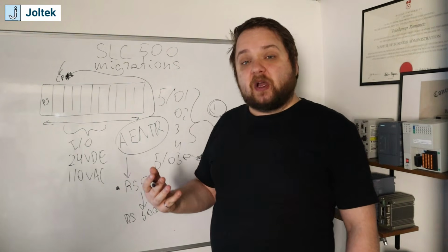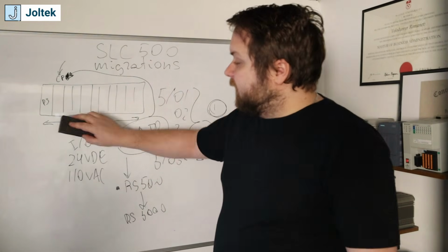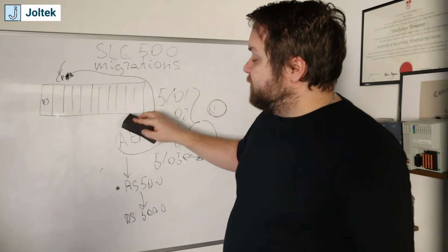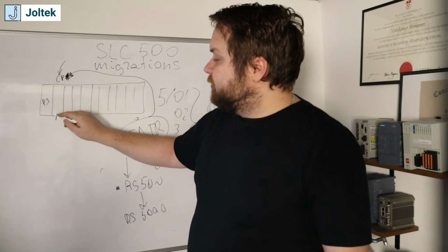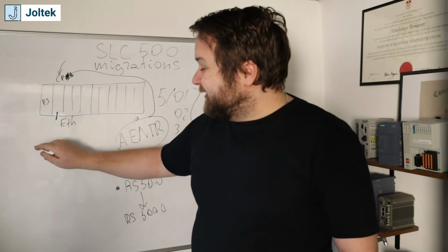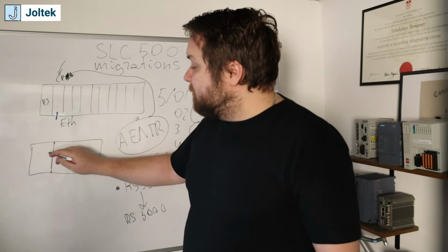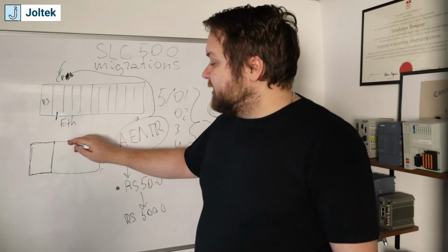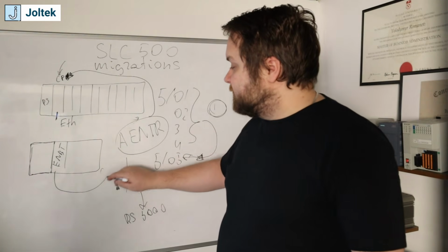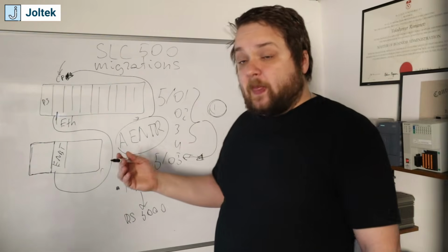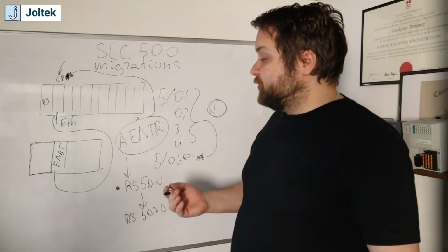Number two, the question then becomes, where does this code actually run? And so this is where an architecture design needs to be discussed, because again, this AENTR card is going to provide you an Ethernet port, which will then tie either to a ControlLogix or a CompactLogix. It doesn't necessarily matter which type, but it becomes a connection. So imagine this is an ENBT card. This is one of the older cards, and this also has a connection, and it goes to the rack, and this becomes your remote rack inside of your tree in RSLogix or Studio 5000.